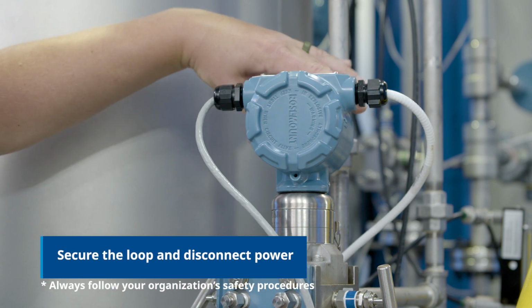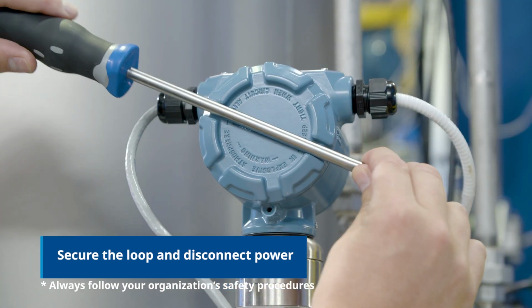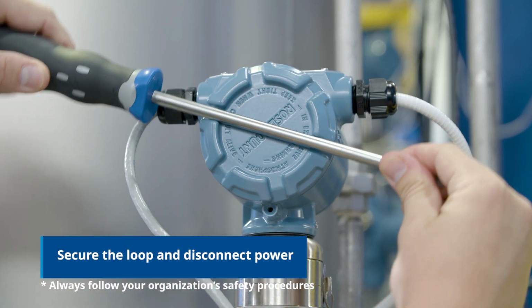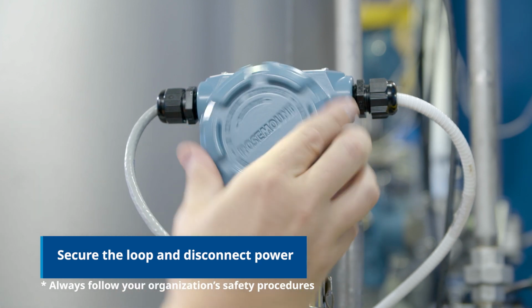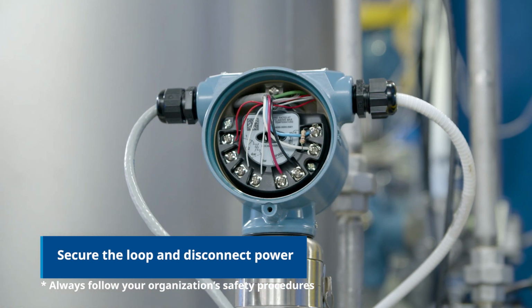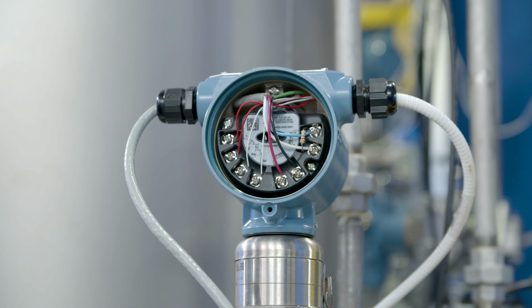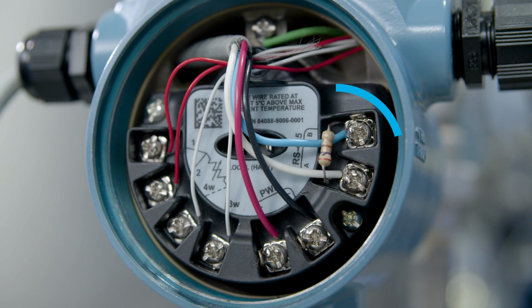Prior to interfacing with the flow computer, you must ensure that the Rosemount 4088 transmitter is powered to product specifications. As with many multivariable wiring techniques, we will utilize the RS-485 terminals in the terminal block to physically connect the transmitter to the flow computer communication bus, while also using a 120 ohm resistor in between terminals A and B.